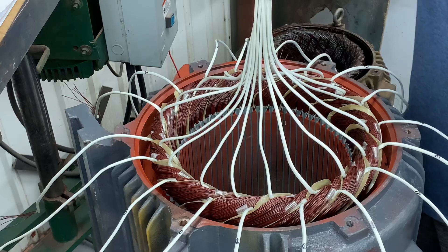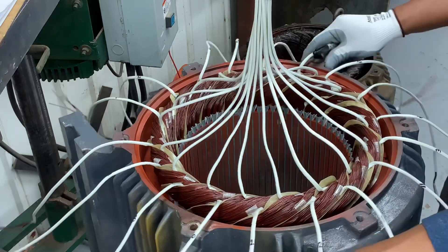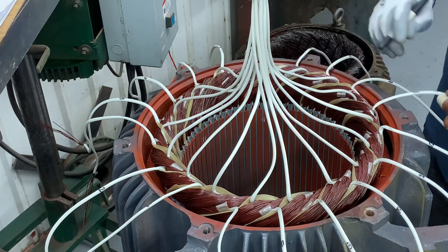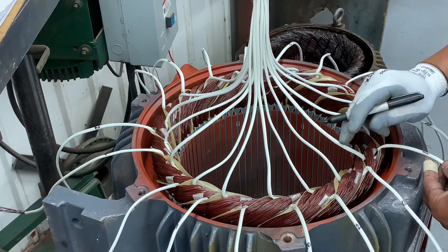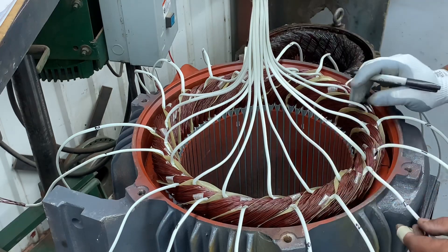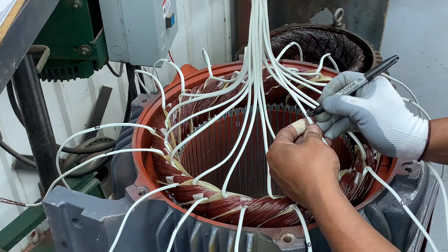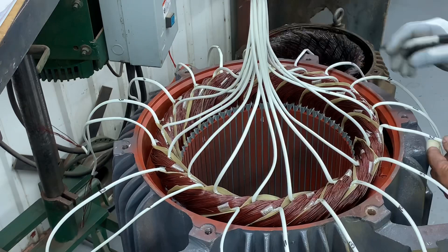So you start here — it's your 1. You get your line here. The end of 1, of course, is 4. The end of 12 should be 9. Those are the simple numbers for motor connection.